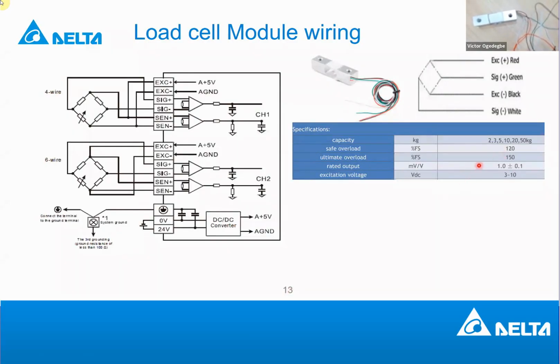So it's very mandatory. If you want to know what this sensor is measuring, if you want the load cell module to have the correct value, you have to select 1 as the gain value, the rated output in the load cell module. So you can see this is the setup. So let's go back now. We switch back the video, and then let's continue. Maybe later I will switch back to the video when we have some load on it.